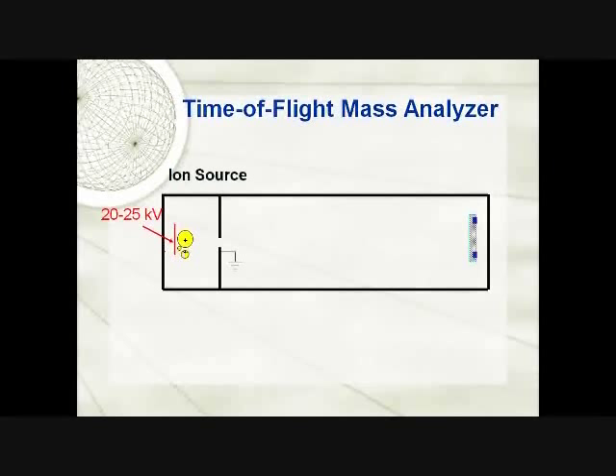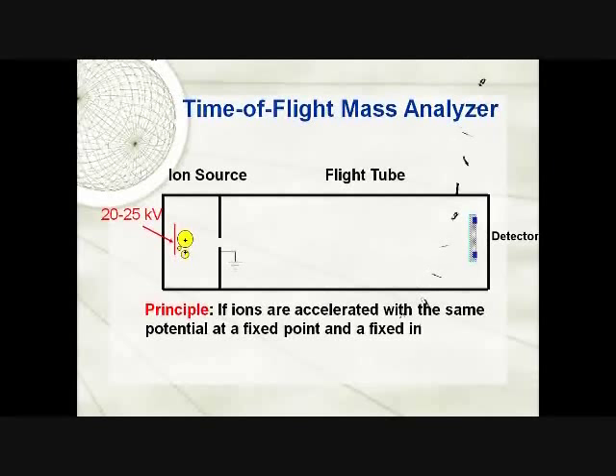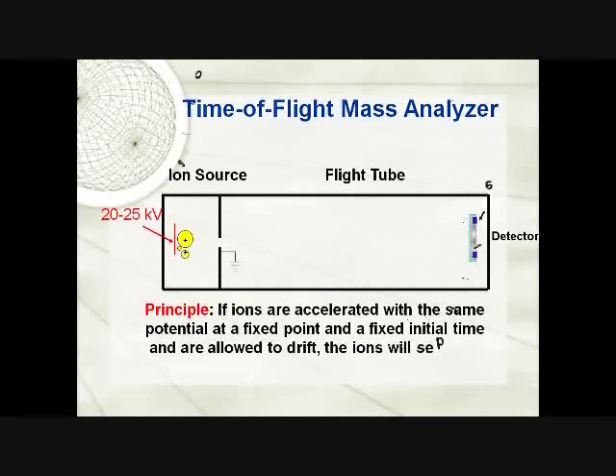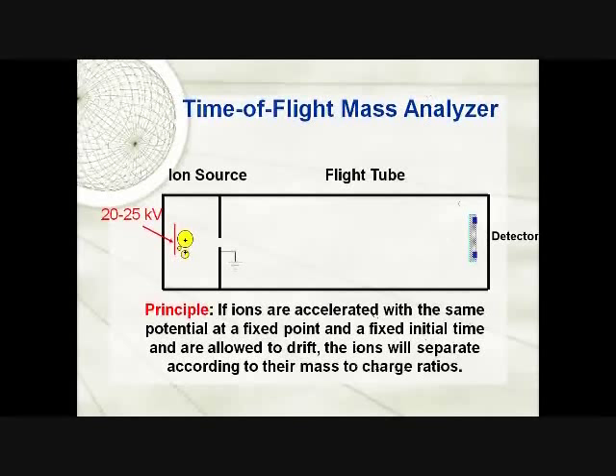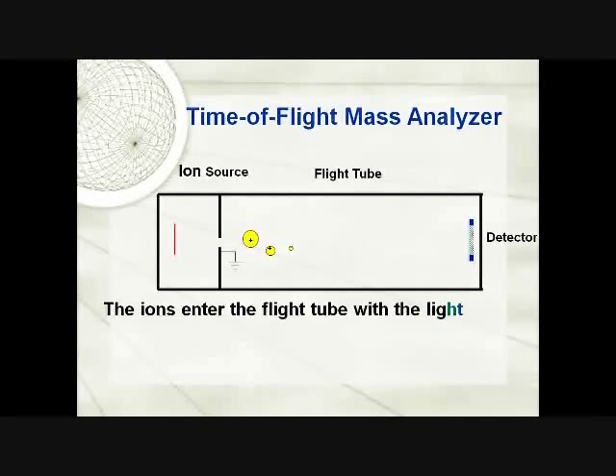The time of flight mass analyzer consists of three components: ion source, flight tube, and an ion detector. In the time of flight mass analyzer, vacuum is created and a potential of 20 to 25 kilovolts is applied on the sample plate containing the sample or matrix. As a result, the sample vaporizes and ionizes, with ions traveling the flight path towards the ion detector. The principle is that if ions are accelerated with the same potential at a fixed initial time and are allowed to drift, the ions separate according to their charge-to-mass ratios. The lighter ions travel faster and reach the detector earlier than the heavier ones. This time of flight can be converted to mass.